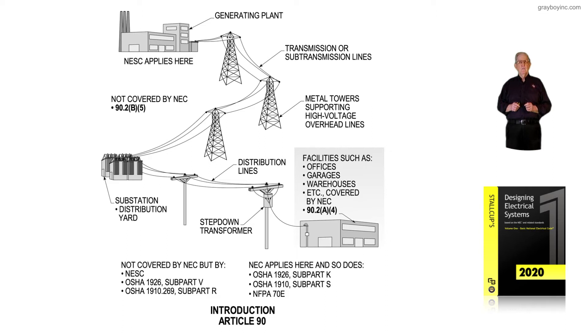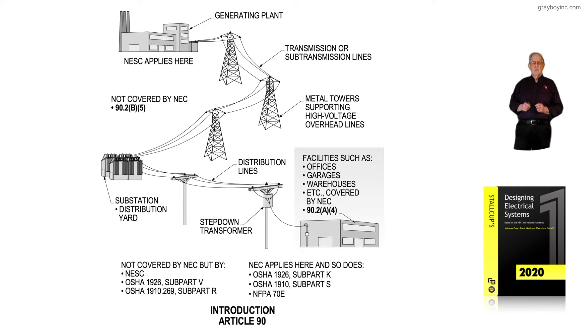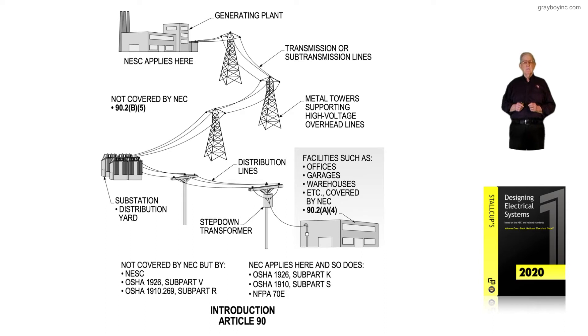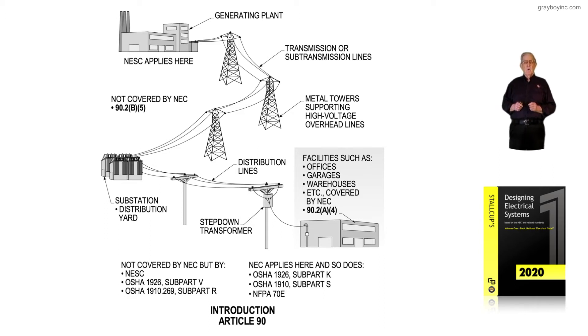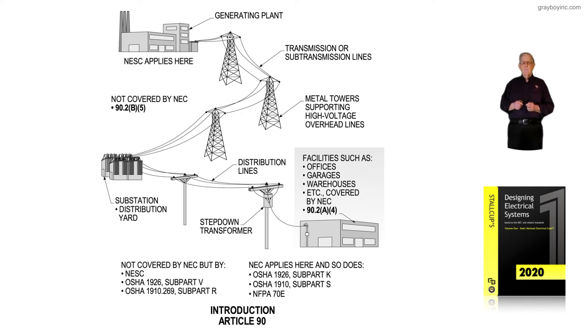That high-voltage transmission line transmits the high voltage into the substation, which steps it down to a distribution voltage — maybe 4,160, 13,800, 13,200, or 12,470 volts, whatever the distribution voltage is for that line. From there, at the transformer on the pole next to the building, it would be stepped down to 120, 208, 277, or 480 volts.